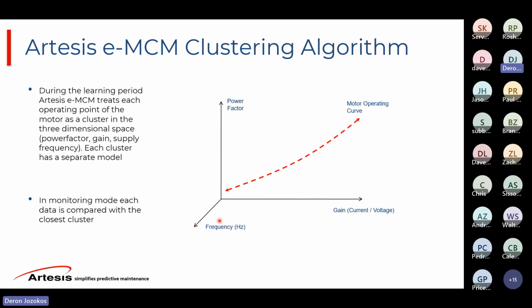Now, the first thing the system does, the EMCMs do, is the model base consists of over 10 million electrical fault signatures. Okay, so that model base is unique to and proprietary to Artesis. And that is really what sets us apart from even electrical signature analysis companies, because the system now knows all these faults. And when you install it, if you have a bad bearing, if you have a misalignment, it quickly identifies those. That's how the AMT Pro works, the portable kit, and is able to find these faults in 7 minutes. The online systems take it a lot further and deeper to find all these faults. So using that model base, the first 3 to 4 days, it's going to identify all of your existing faults and report them to you.